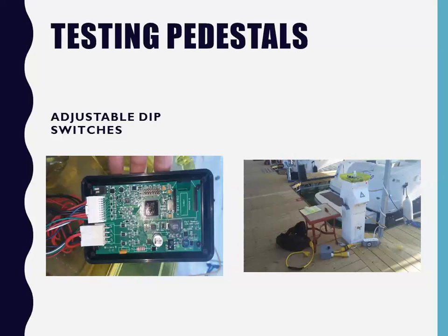and installed the RF bags to get rid of the RF problem in case somebody had strong enough radar, VHF antenna close enough. You know, anything in the air can set these things off.